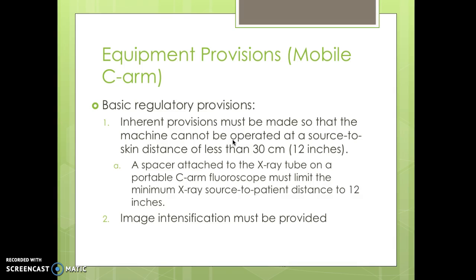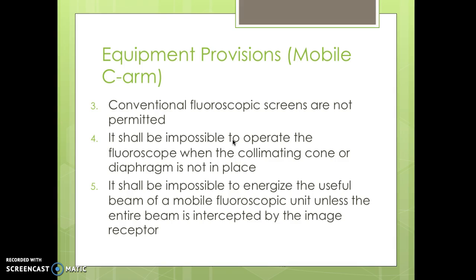So, basic regulatory provisions: inherent provisions must be made so that the machine cannot be operated at a source to skin distance of less than 30 centimeters, which is 12 inches. A spacer attached to the X-ray tube on a portable C-arm fluoroscopy unit must limit the minimum X-ray source to patient distance to 12 inches, and image intensification must be provided. Conventional fluoroscopy screens are not permitted. It should be impossible to create a fluoroscopic image when the collimator cone or diaphragm is not in place, so that's the spacer. And it should be impossible to energize the useful beam of a mobile fluoroscopy unit unless the entire beam is intercepted by the image receptor.